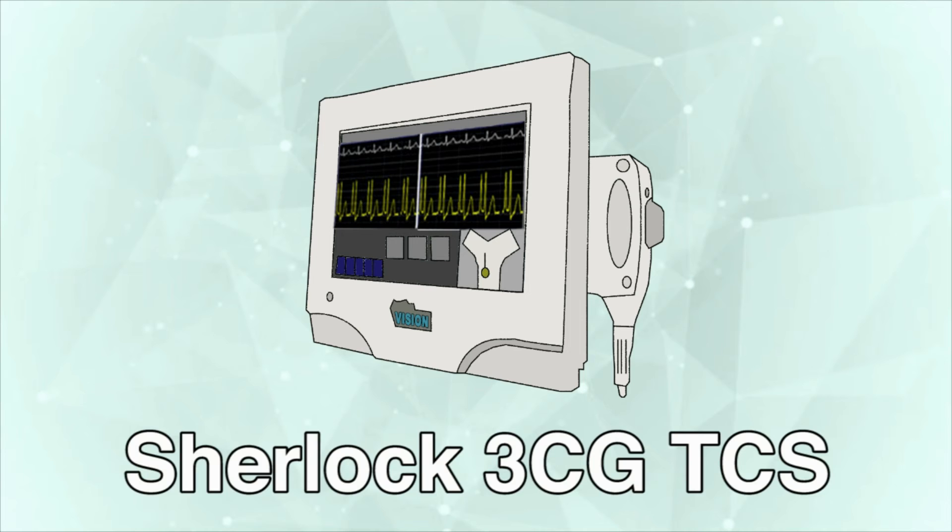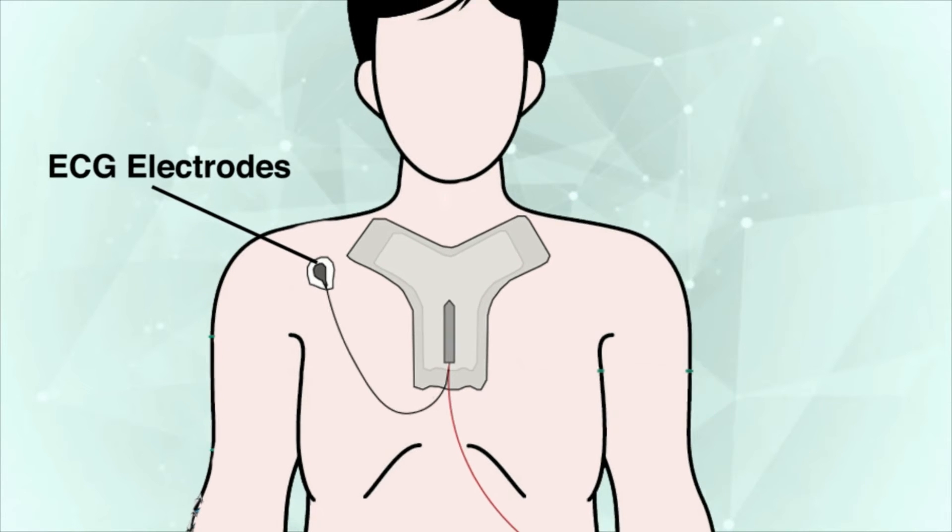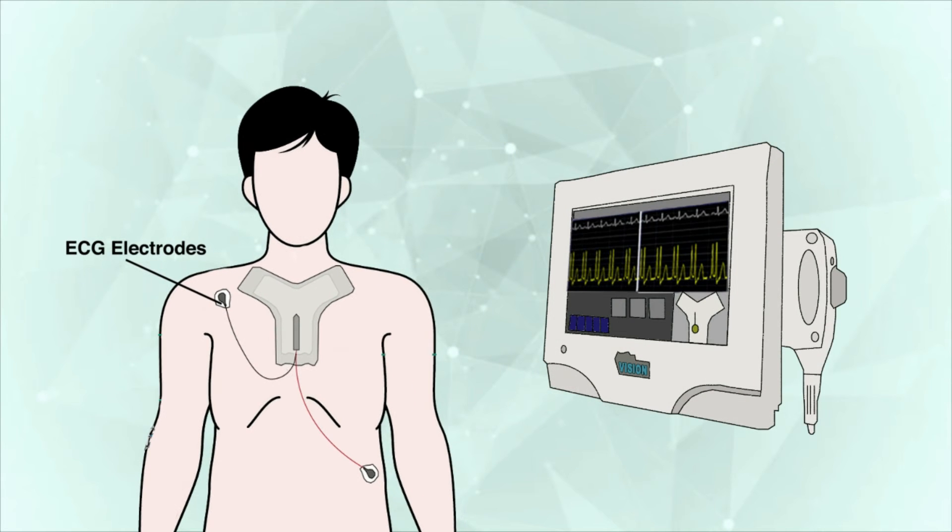The SHERLOC 3CG TCS is an alternative tip confirmation method to fluoroscopy or chest x-ray for PICC tip insertion confirmation in adults with a distinct P-wave in their ECG signal. Providers place a sensor on a patient's chest, and two ECG electrodes are placed on the patient's torso. Using these electrodes and a specific catheter with an intravascular electrode, the system gathers the patient's cardiac electrical activity. Using the SHERLOC 3CG TCS display monitor, providers see real-time tip location to aid in correct tip placement.